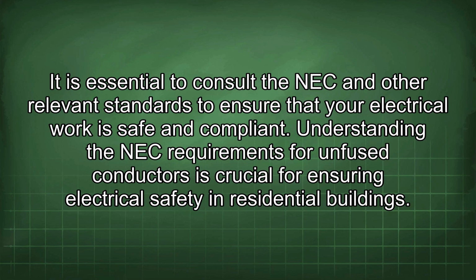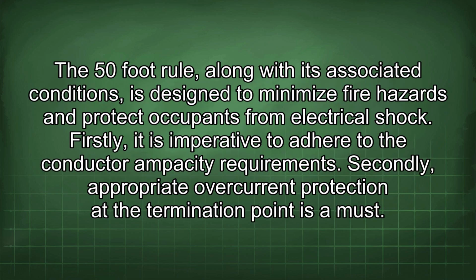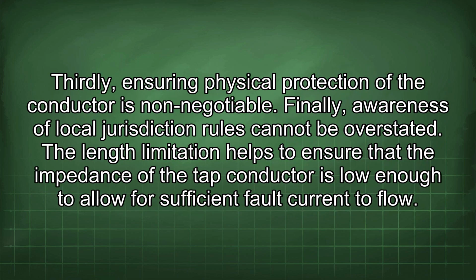Understanding the NEC requirements for unfused conductors is crucial for ensuring electrical safety in residential buildings. The 50-foot rule, along with its associated conditions, is designed to minimize fire hazards and protect occupants from electrical shock. Firstly, it is imperative to adhere to the conductor ampacity requirement. Secondly, appropriate overcurrent protection at the termination point is a must. Thirdly, ensuring physical protection of the conductor is non-negotiable. Finally, awareness of local jurisdiction rules cannot be overstated. The length limitation helps to ensure that the impedance of the tap conductor is low enough to allow for sufficient fault current to flow.